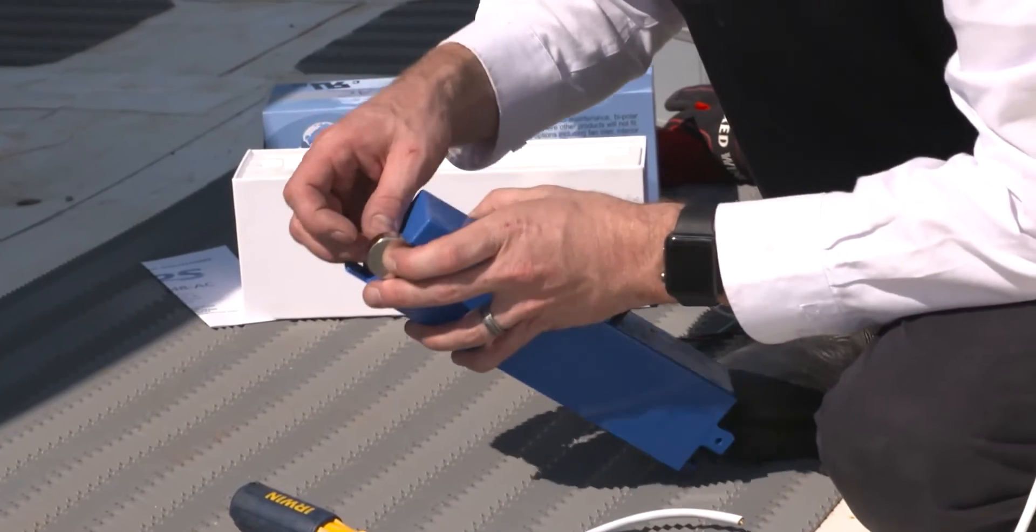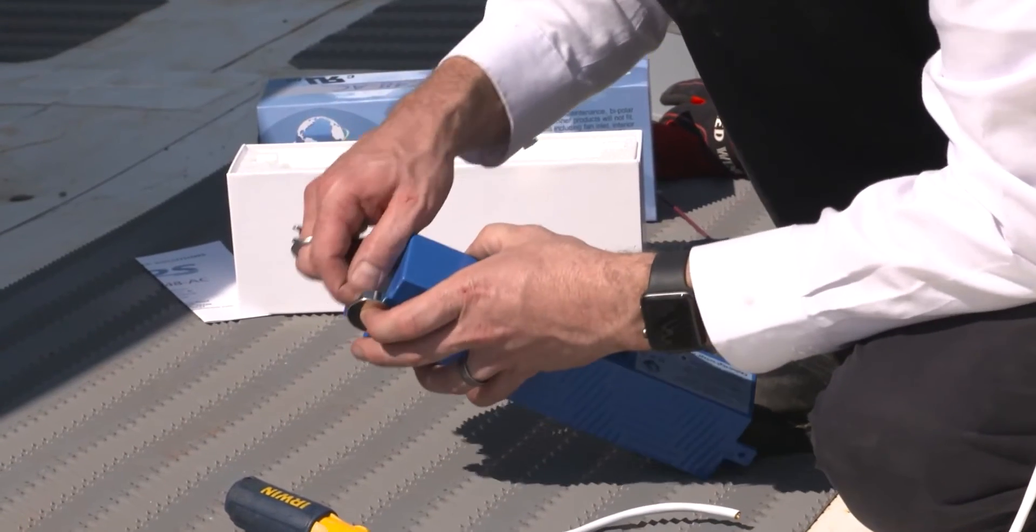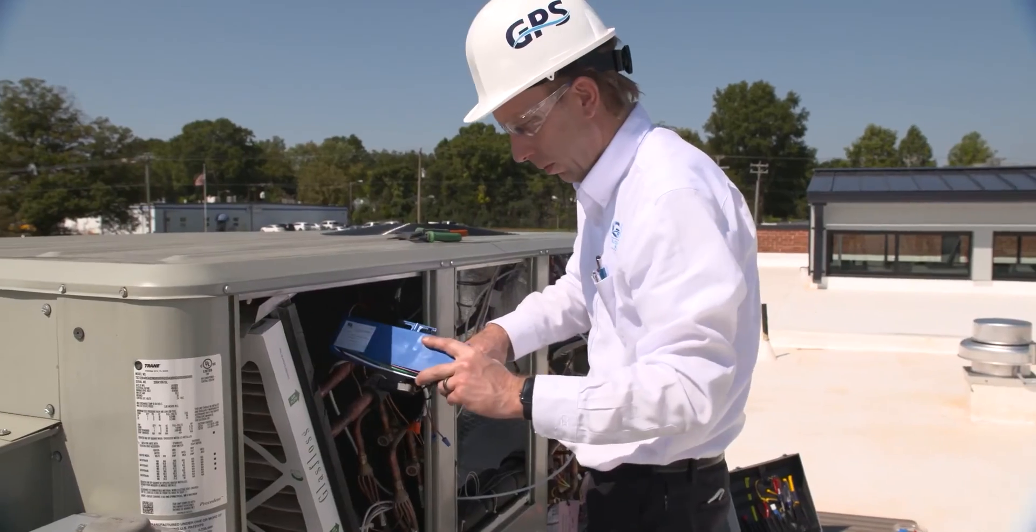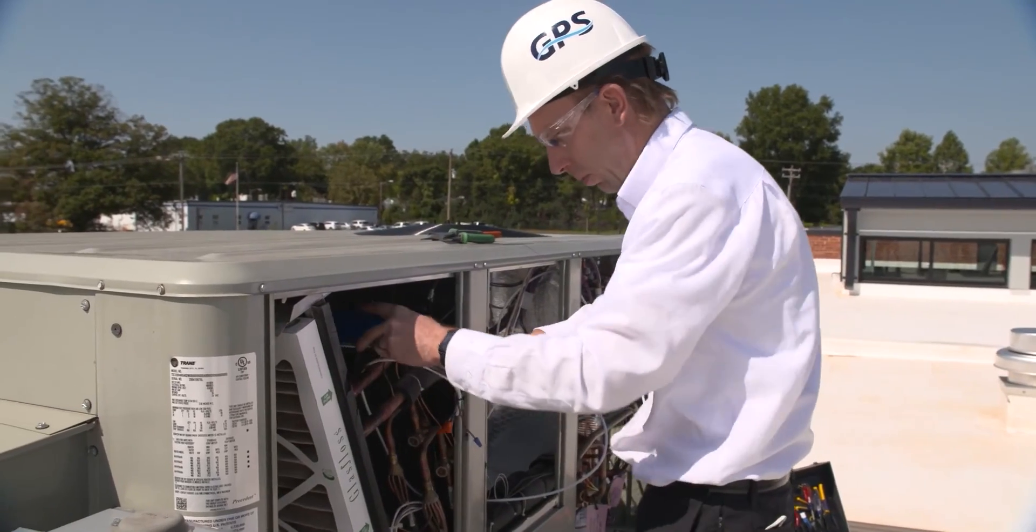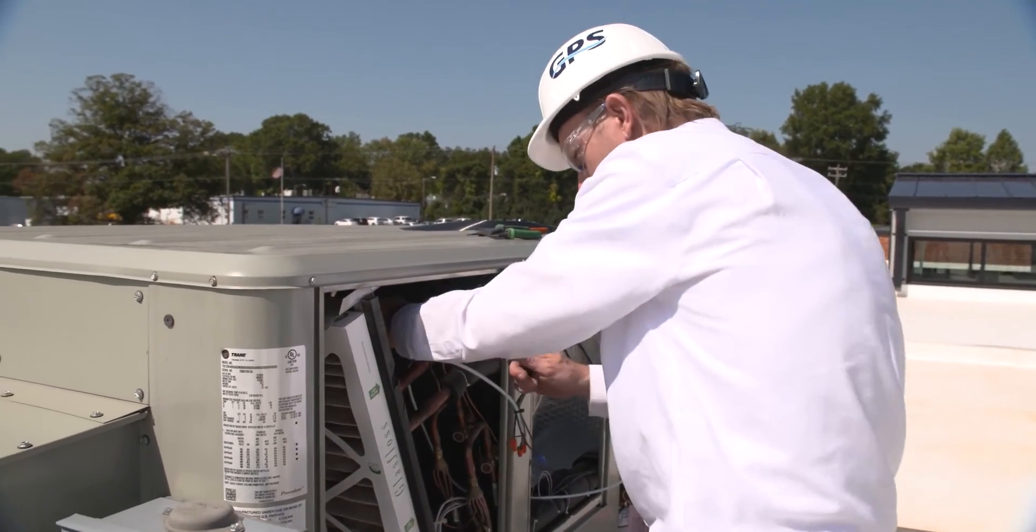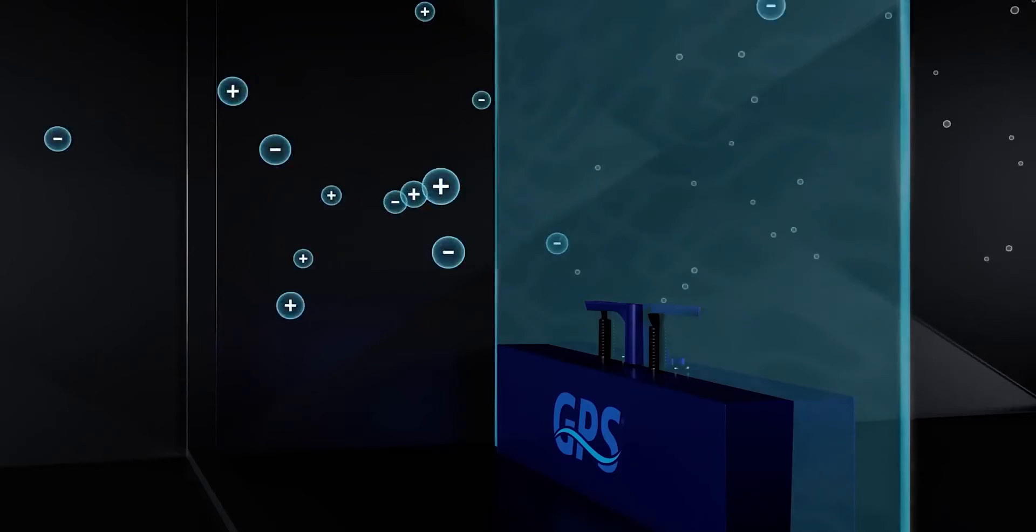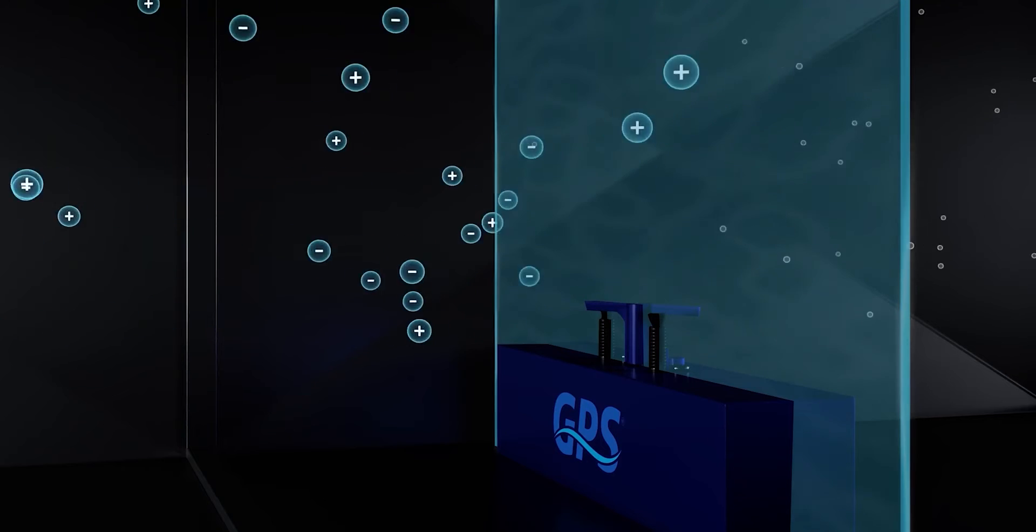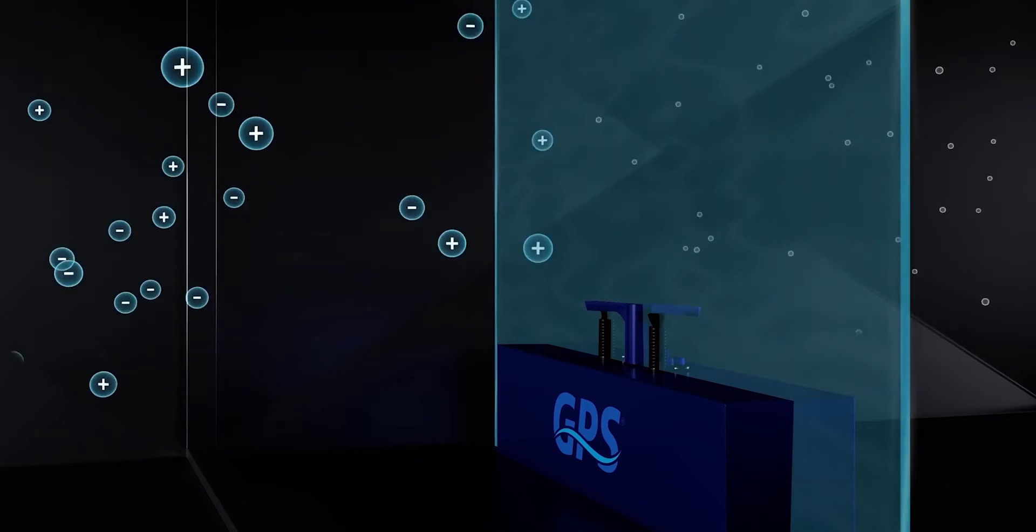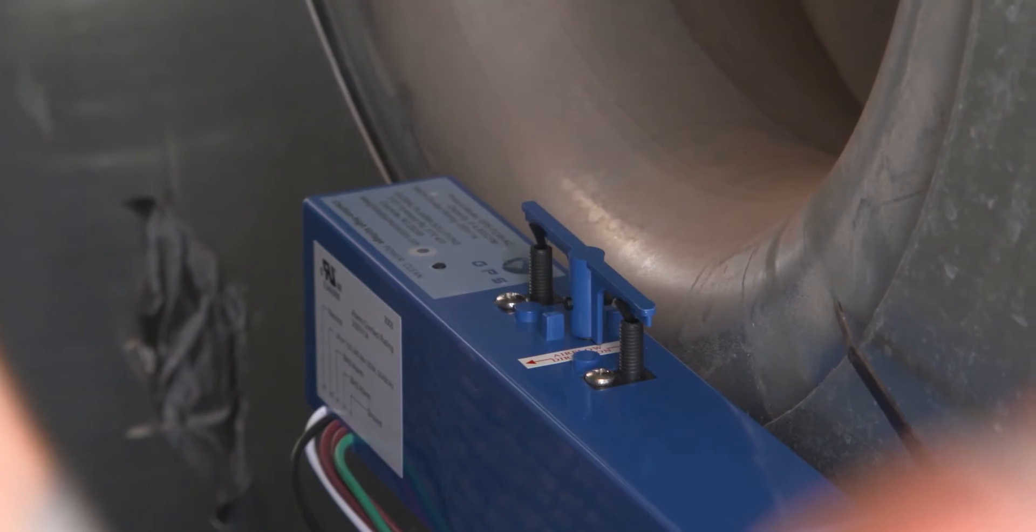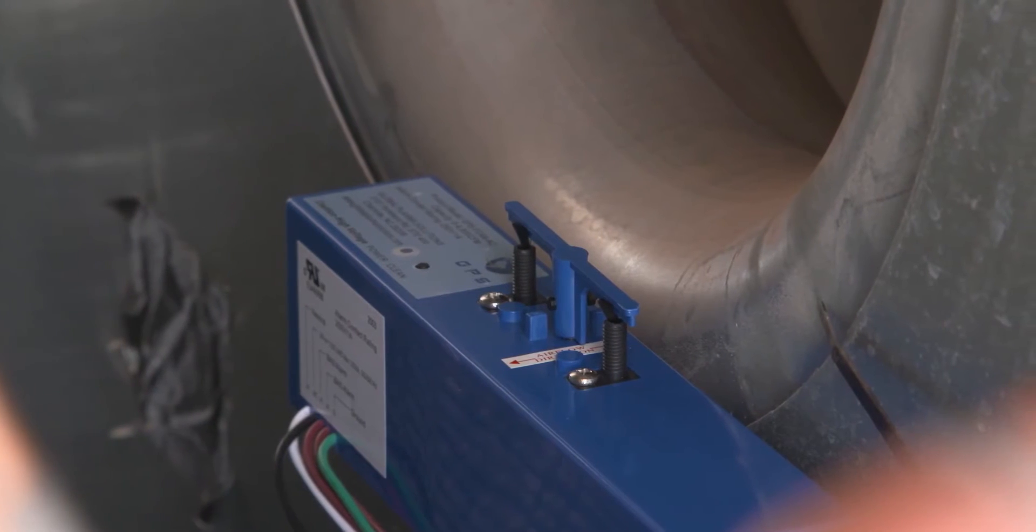Mount the magnets to the FC48AC. Install the FC48AC so that airflow is passing through both emitters at the same time like a football through goalposts. Check that the wiper arm has room to rotate freely.